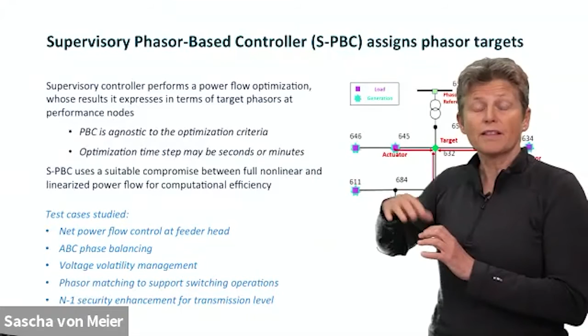You can also choose, for example, a performance node out at the end of the feeder where there might be a tie switch to connect it to a neighboring circuit. You could watch the phasor on the neighboring circuit and drive the phasor at your end to the same value, so then it becomes safe to close a switch, and it can help you reconfigure the system on the fly.